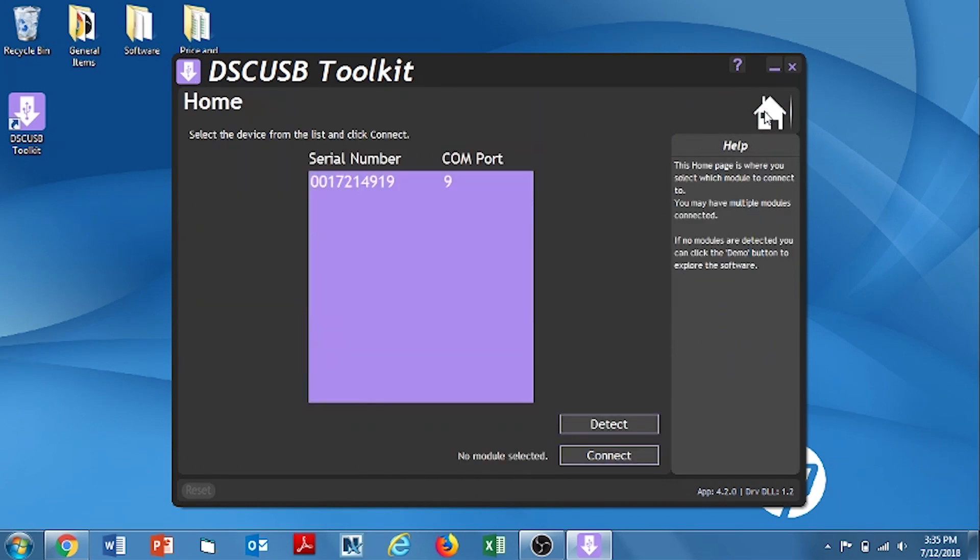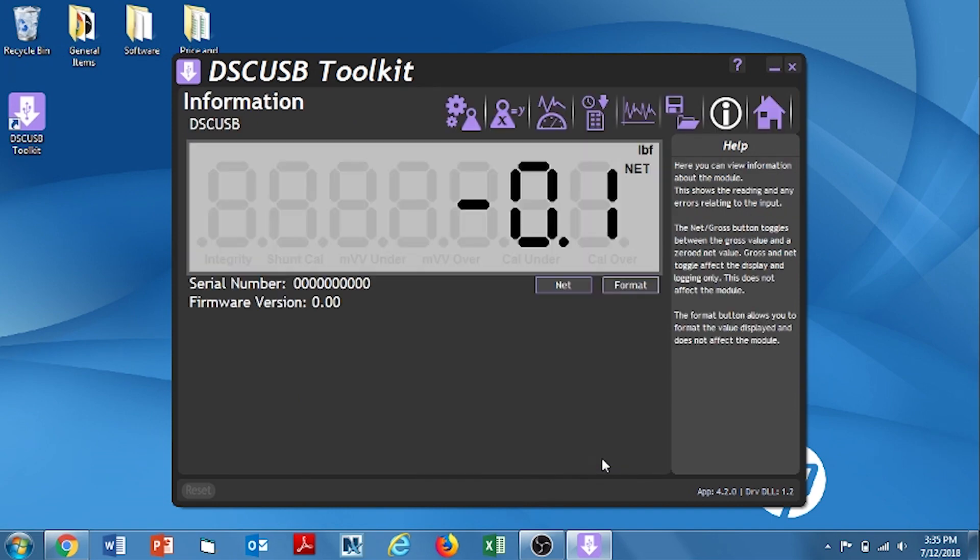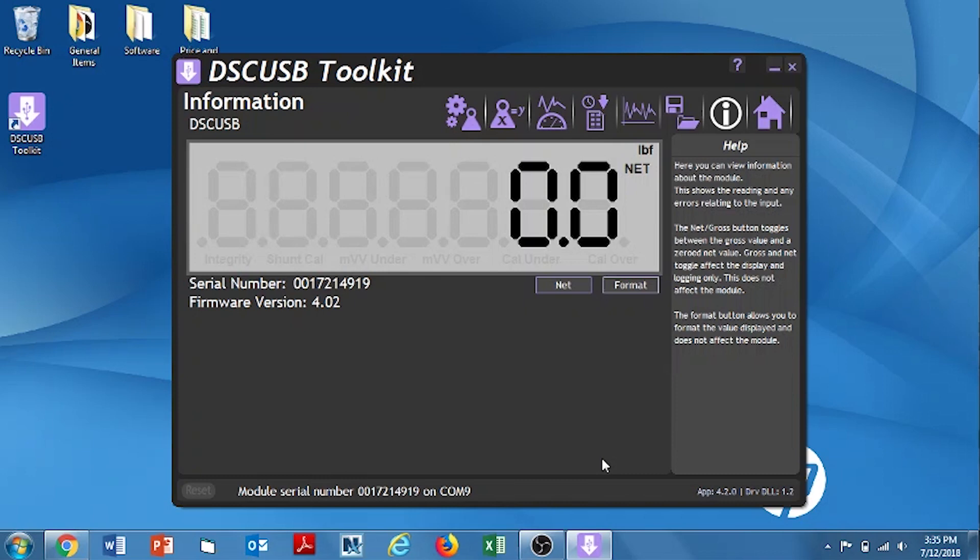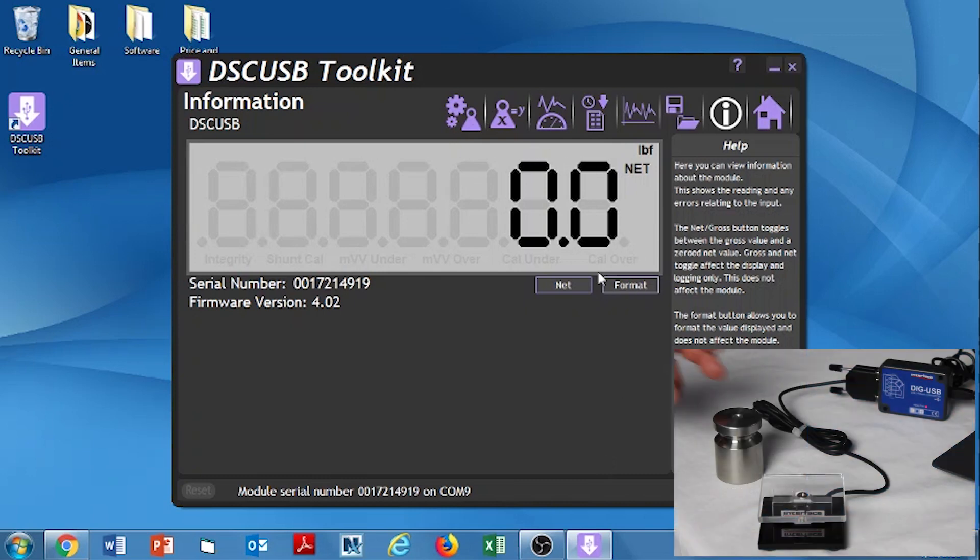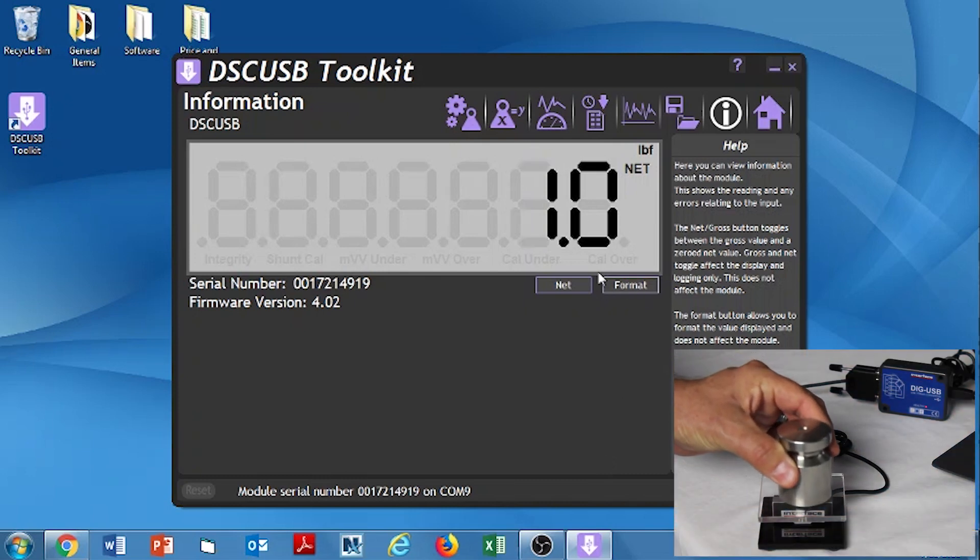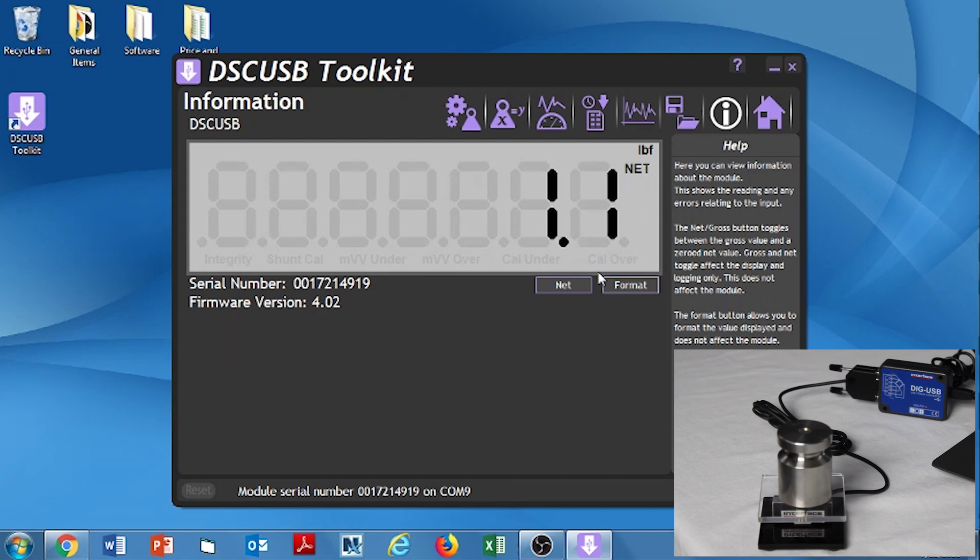And now we're just going to go and verify that this calibration was correctly performed. I'm going to hit the home button. Select the serial number and connect. Make sure it's reading zero on the screen. And I'm going to apply the weight. And if I get 1.1, then we have a successful calibration. We do. And now you're good to go.